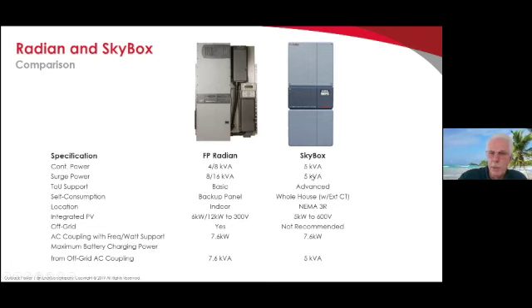It's a transformerless design, and it's that transformer that gives the surge capability with the Radian. So with a 4 kVA Radian, you get 8 kVA surge. Likewise, with the 8 kVA Radian, you get 16 kVA surge. And that's the 100 millisecond spec. Those first 5 cycles of a motor turning on is usually adequate to handle that surge.